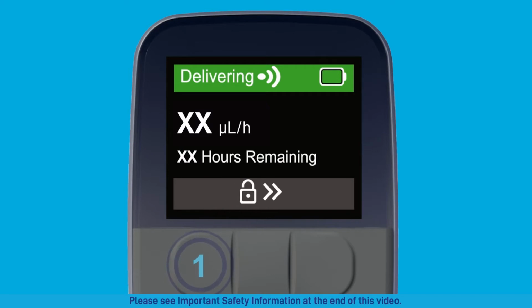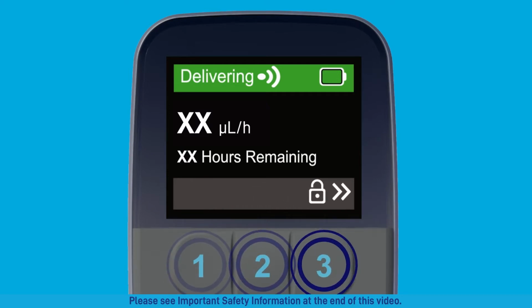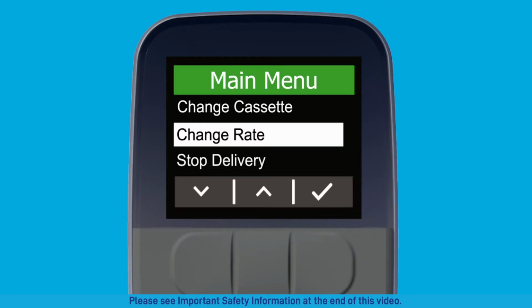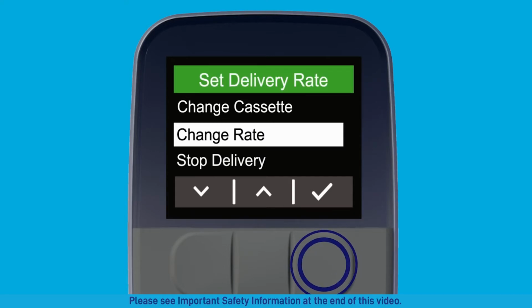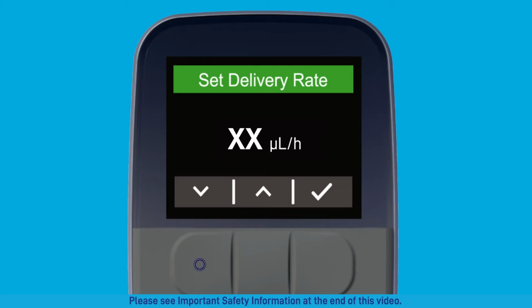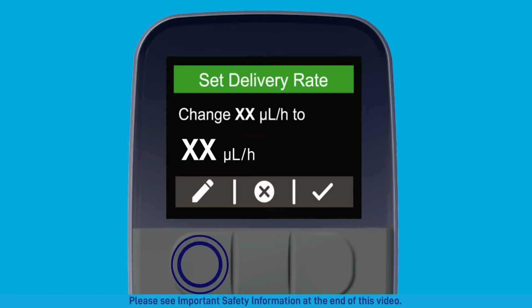First, press each front button left to right to unlock your screen. Then, use the front buttons on your remote to highlight the Change Rate menu option and press the check mark to select it. Use the arrows to change your prescribed rate. Then, press the check mark to continue. You can select the pencil to edit your rate, the X to cancel your rate change, or the check mark to confirm your new rate.